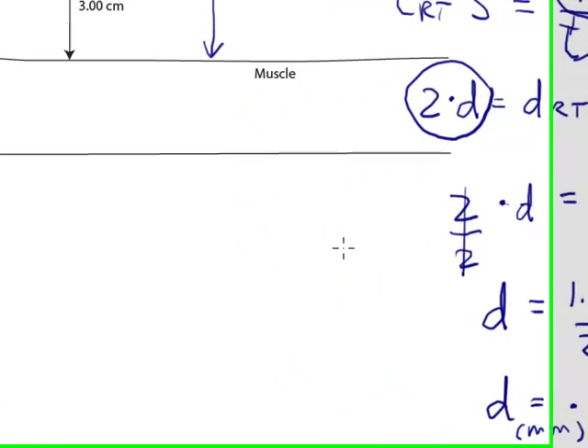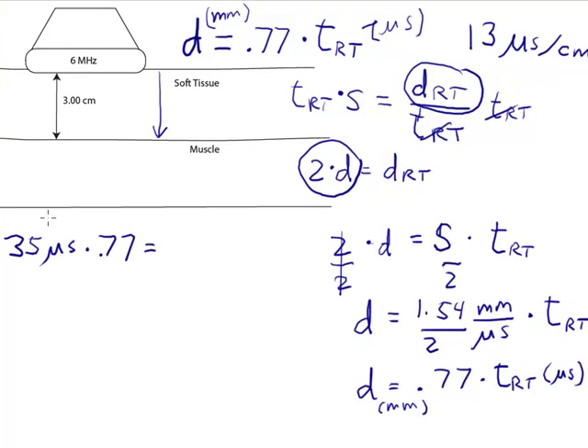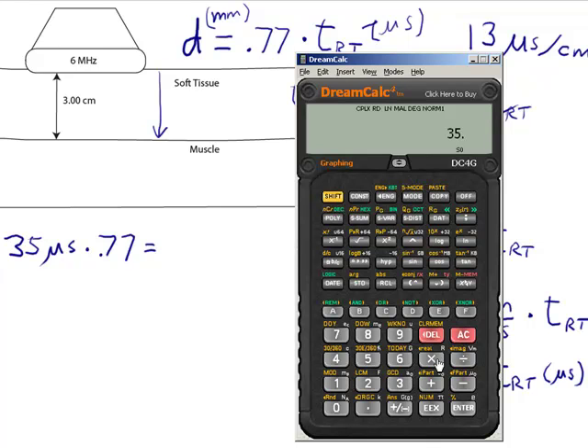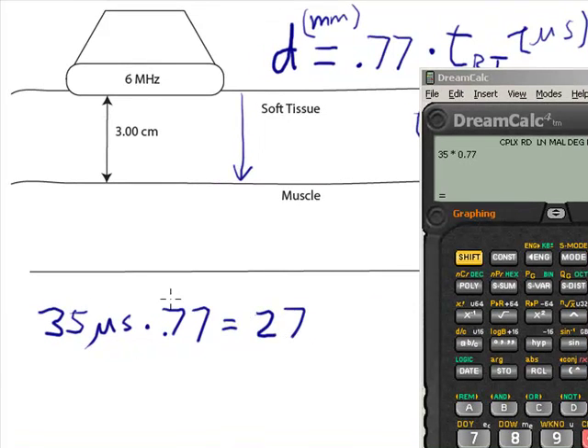So let's look at an example of this. Let's say that I have a signal that returns 35 microseconds after it was emitted from the transducer. All I have to do is multiply by 0.77 and I can figure out the distance away that the reflection was. So 35 times 0.77 equals 27.